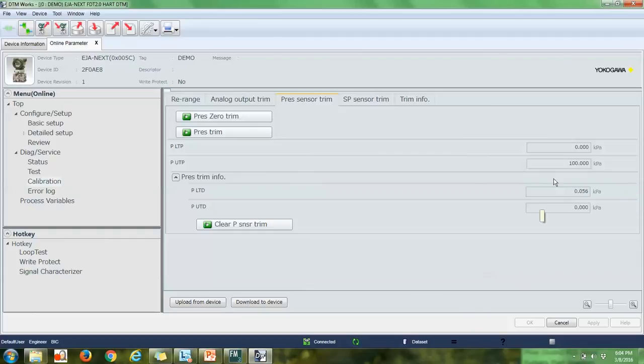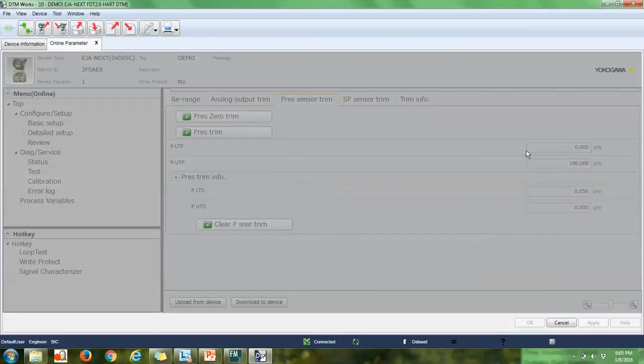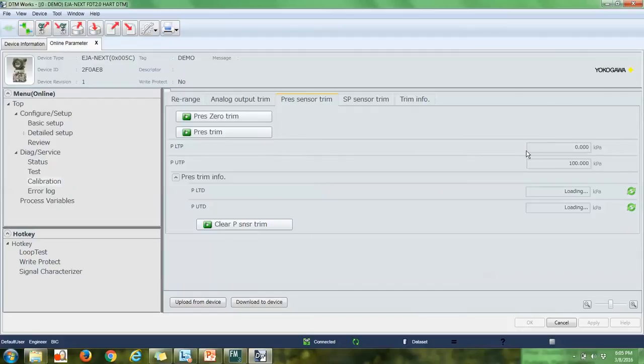Now in the pressure trim info, we can see that lower trim adjustment I made, because the transmitter was reading a little bit negative, so it kept a record of that. One nice thing about Fieldmate and the Yokogawa pressure transmitter is that if you make a trim and make a mistake, you can reset it back to factory settings with this button, clear pressure sensor trim. When I do this, it will return the trim back to what the factory originally set. So if you make a mistake, it's not a big issue. Okay, so we trimmed our transmitter. That was the big goal after doing the calibration.